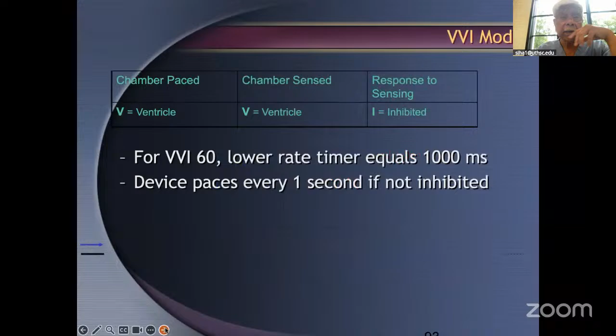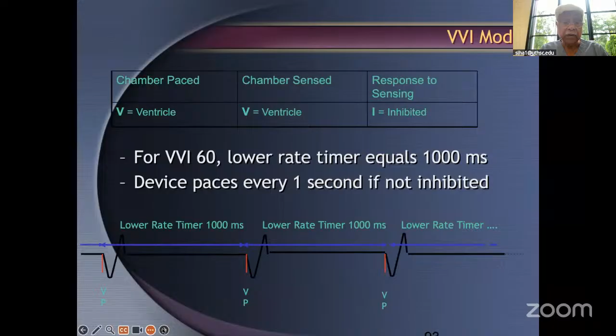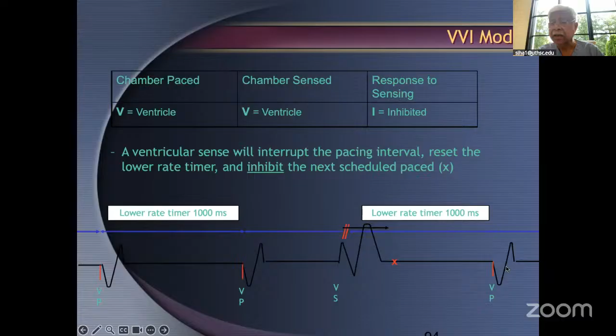So watch this video. V-paced, V-paced, V-paced, that's a VVI mode. Why is it VVI mode? Here V-paced, and the PVC comes. If the PVC comes in the VVI mode, it will inhibit the pacemaker, and then the timing will start from here, where it senses. From here to here, the same distance. If it is 60 beats per minute, that means 1,000 milliseconds. Here, the sensing comes, it inhibits the pacemaker, but again, the time cycle starts from here to here. That's a VVI mode.